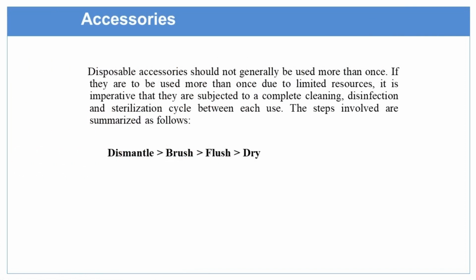Accessories we must disassemble, brush, flush and dry. All the accessories we use during procedures must first be disassembled, then flushed of all organic material, then dried, packed, and sent. If those accessories are for sterilization, plasma sterilization, send to CSSD, and if not, we should use high-level disinfection.